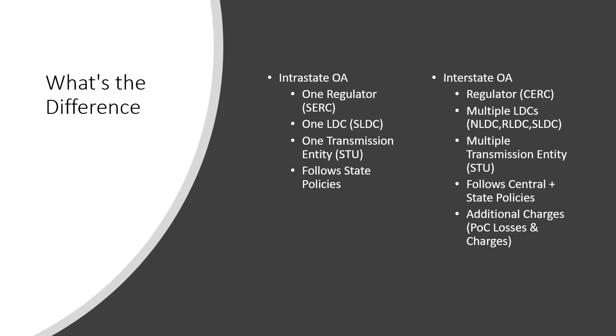Coming to interstate open access, where multiple states are involved, the regulator becomes the Central Electricity Regulatory Commission (CERC), as per the Electricity Act. Since there are multiple states involved, you might procure power from the western part of India while your plant is in the eastern part. Power would flow from the western region to the eastern region, scheduled through the Western Regional Load Dispatch Center (WRLDC) to the Eastern Regional Load Dispatch Center (ERLDC), and you also deal with the State Load Dispatch Center at the consumption end.